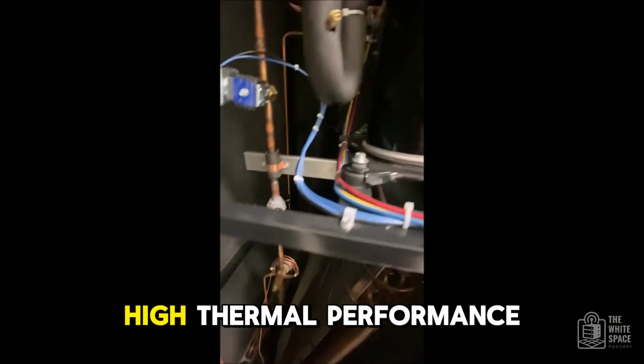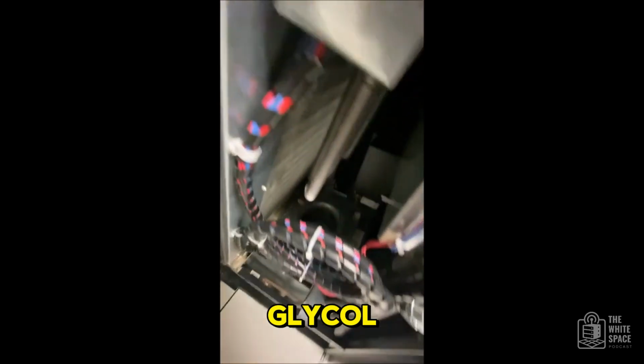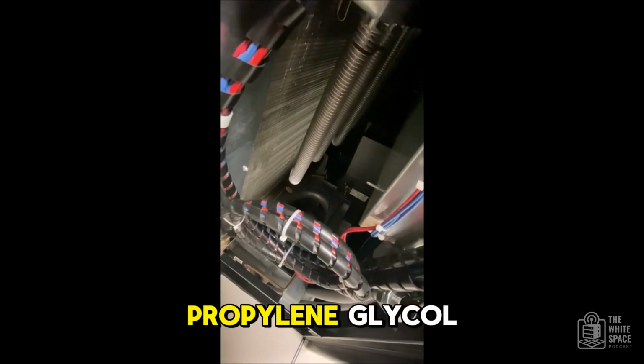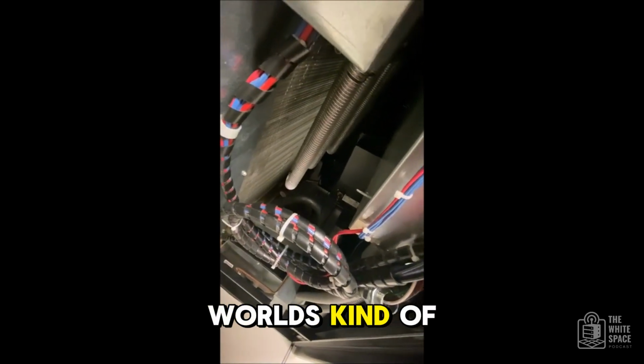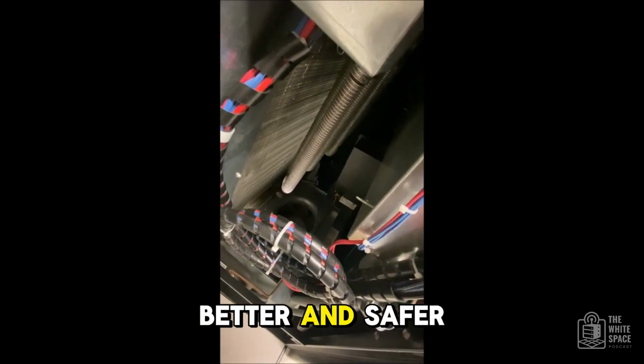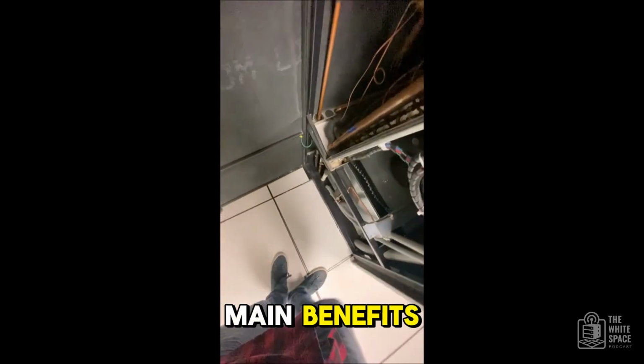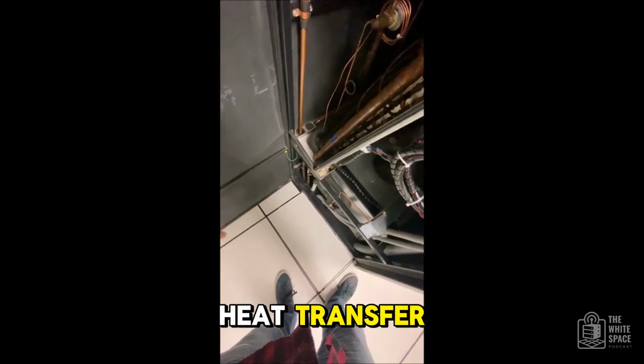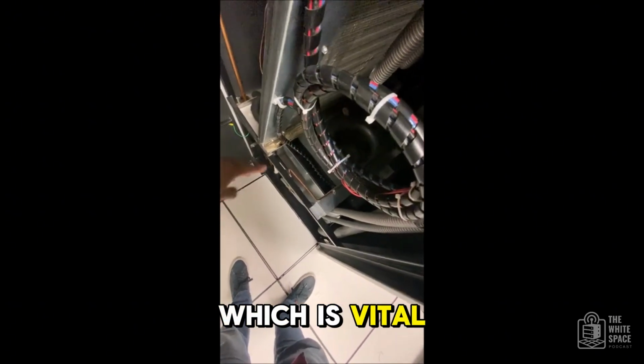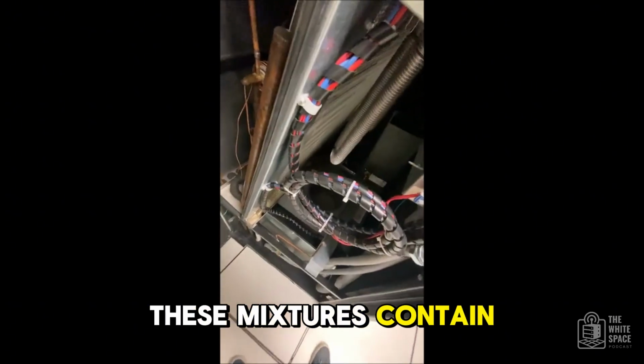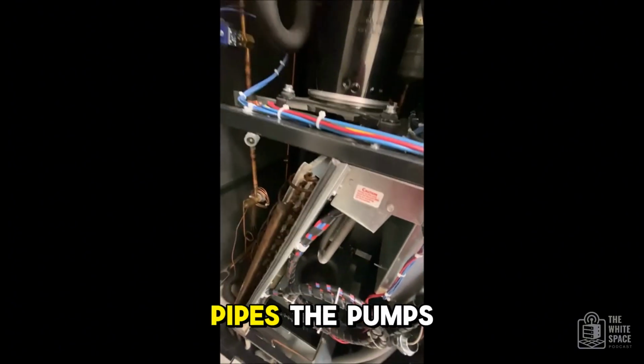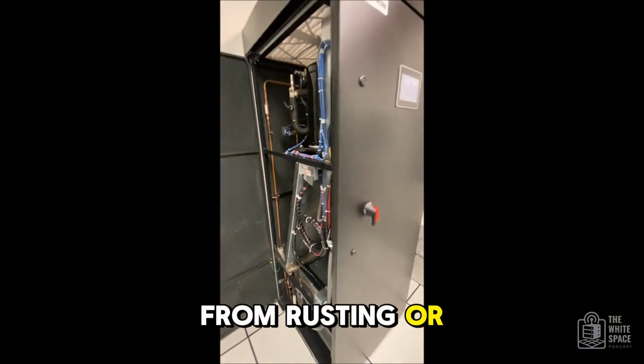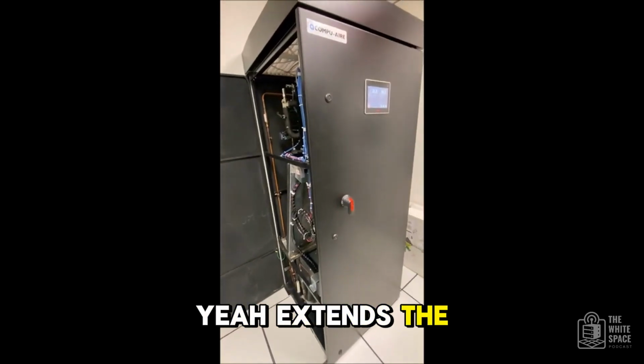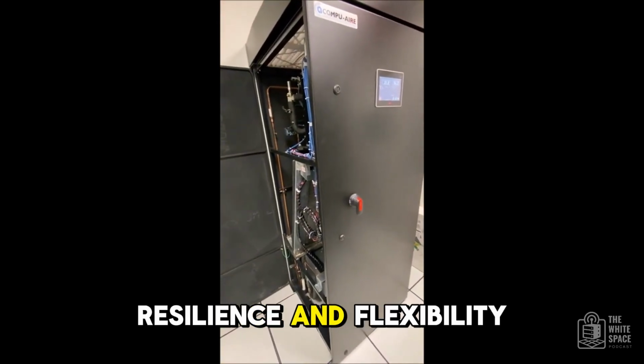It's designed to give you the high thermal performance closer to ethylene glycol, but with the safety profile of propylene glycol. Best of both worlds, kind of. So it makes the coolant work better and safer. What are the main benefits glycol brings? Better heat transfer, that freeze protection, which is vital. And importantly, these mixtures contain corrosion inhibitors. They protect the pipes, the pumps, the cold plates from rusting or degrading over time. Extends the life of the whole system. It just adds resilience and flexibility.